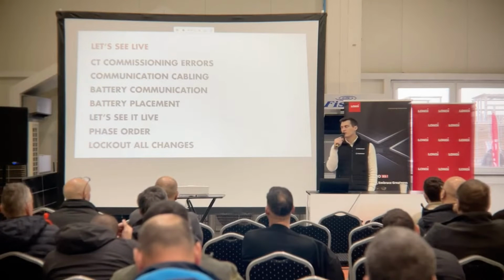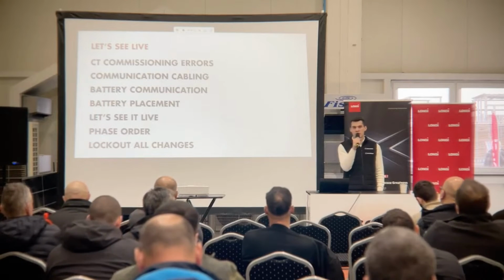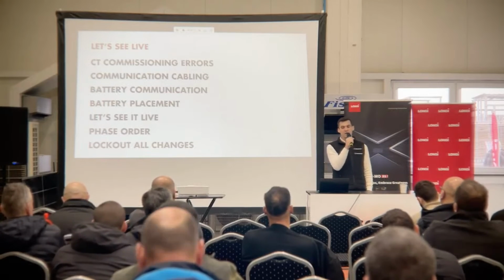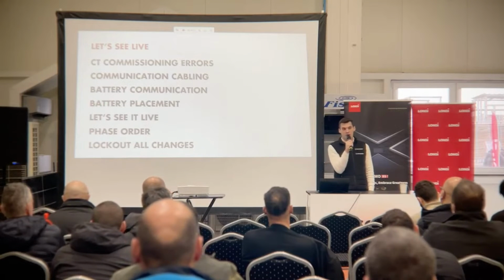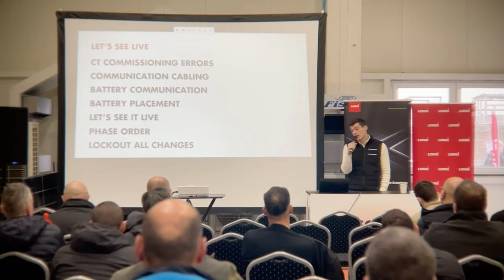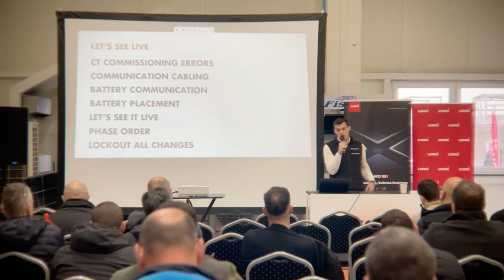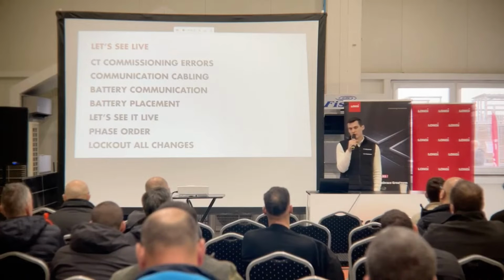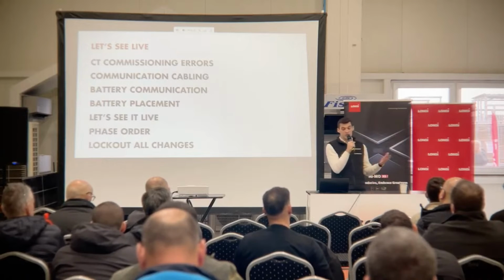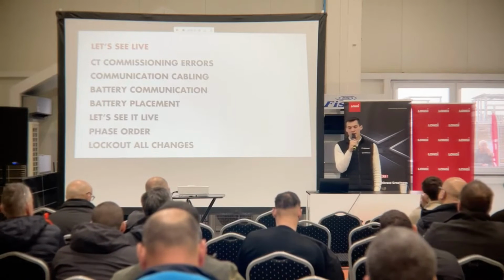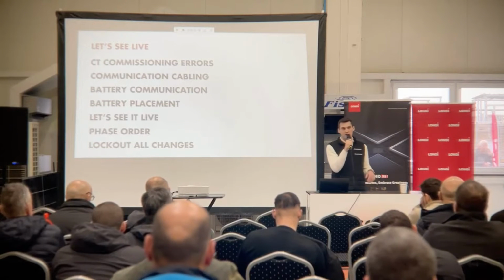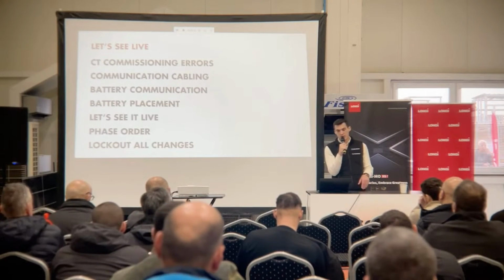These are instead of smart meters. Sometimes you can use smart meters when the distance between the metering point and the inverter is way too long or way too big. Then you need to purchase an additional smart meter, because the signal from the CT will not be strong enough to reach the inverter, let's say. But the smart meter provides a communication signal instead of just a current. So you can use a repeater within the line and it will strengthen the signal.